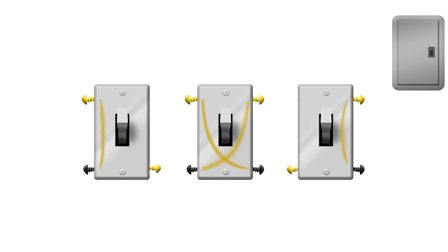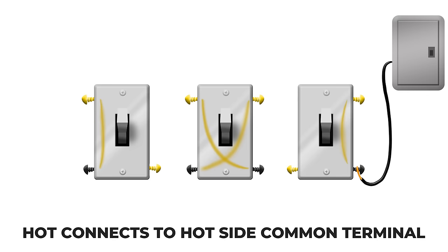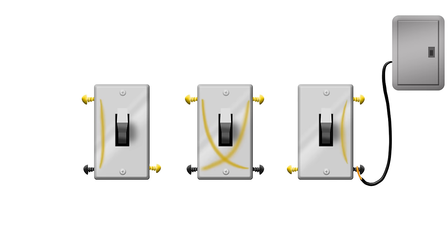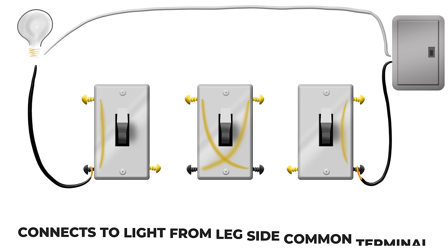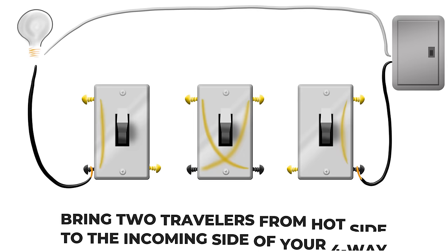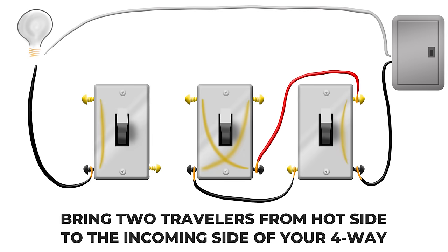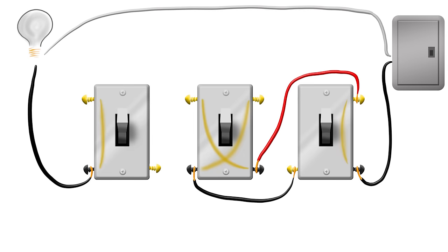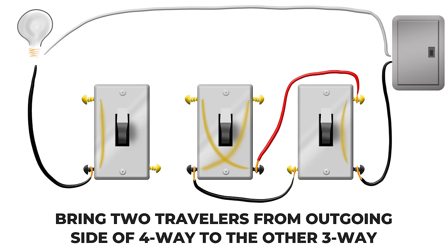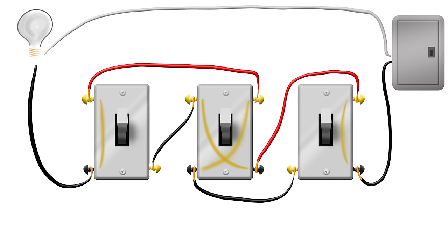So again we're going to have our hot side. That's where current comes into the circuit and then out here your switch leg that goes up to your light. From your hot side you're going to bring two travelers to the incoming side of your four-way. Then from the outgoing side of your four-way you're going to have two more travelers that go to the next three-way.